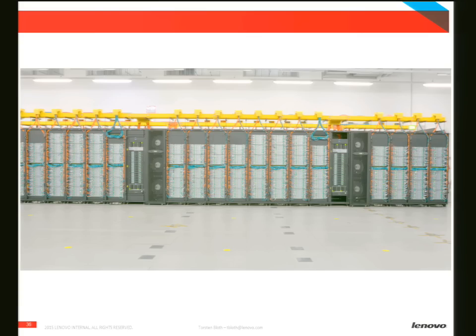But even with 45 degrees inlet, it will be 50 to 55 degrees C outlet temperature, of course. And it's still okay, even in very hot summers, to get free air cooling. In the Munich area, you don't get 50 degrees outside, even if it's very hot; you get 40, 45 degrees. And that still makes it possible to cool the system and the water with free air, which is free, of course, right? So that's the reason they can operate the system at a PUE level of 1.1.